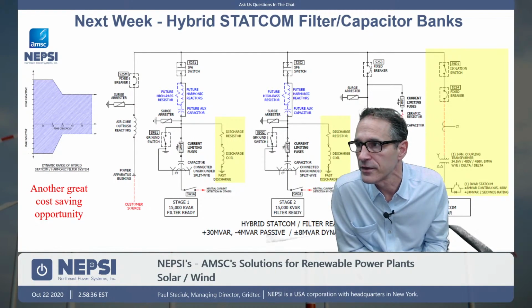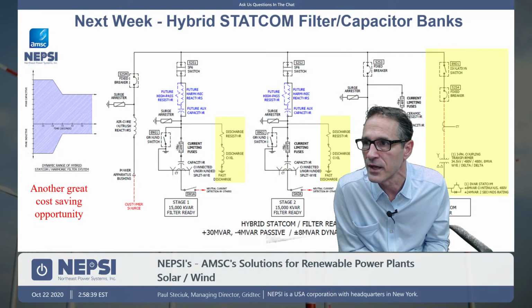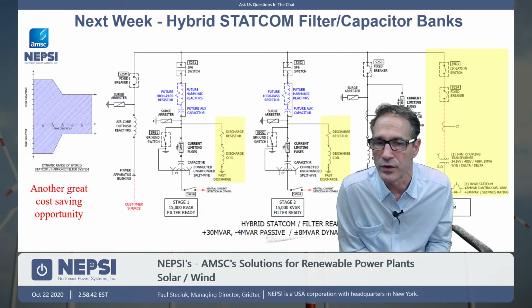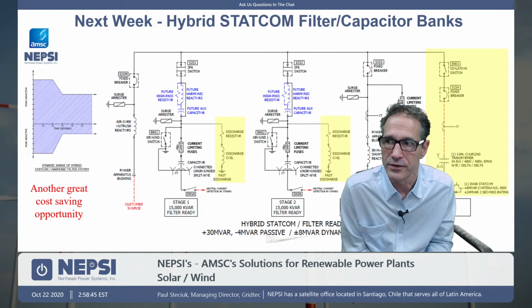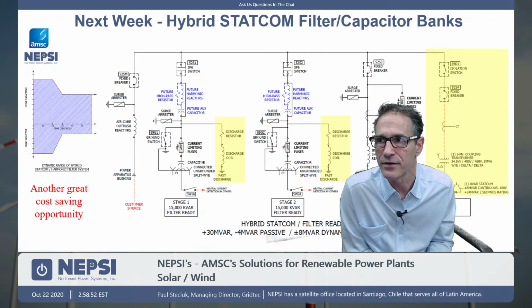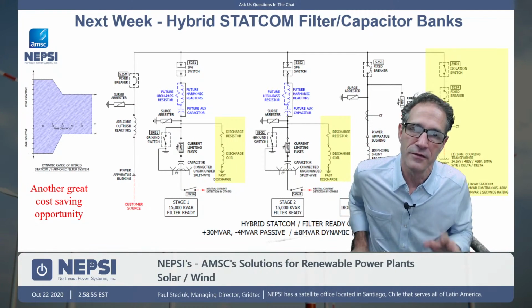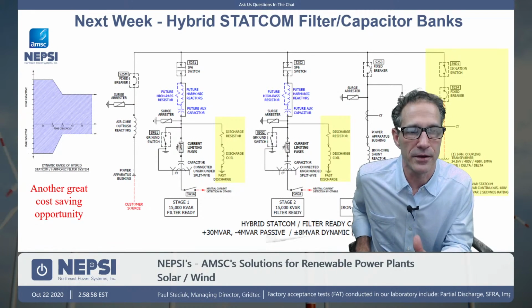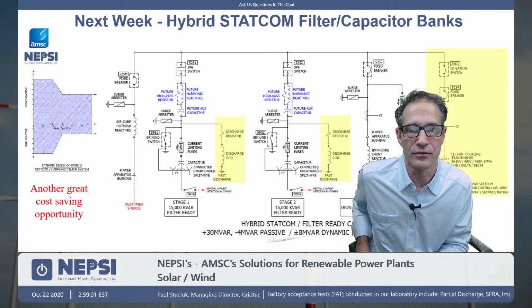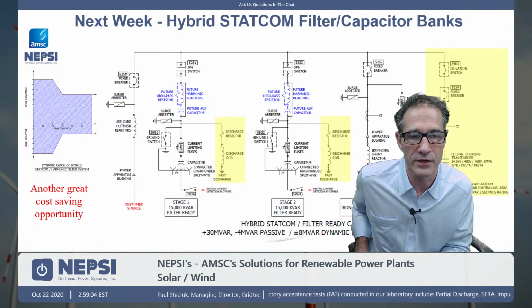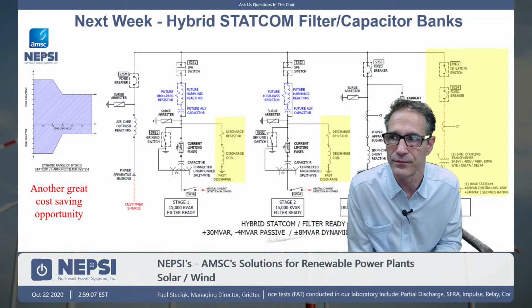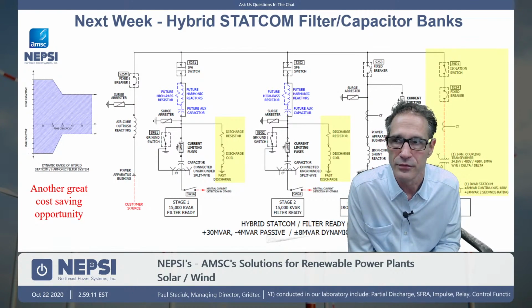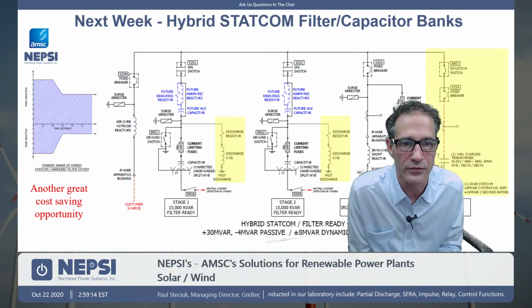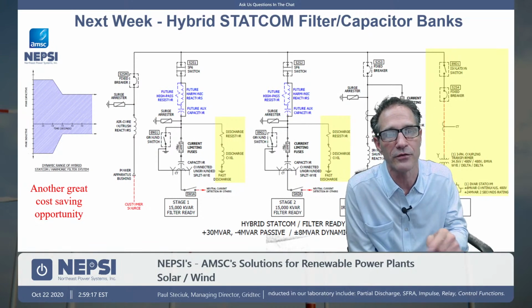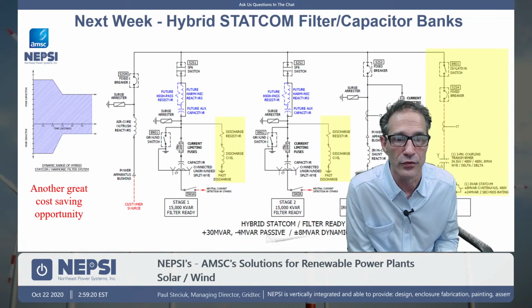Okay, so Talit asked, what is a good filter type to dampen natural harmonic resonance point at around the 40th harmonic? Here I would say that you would want to consider a C high pass filter. No, actually, I take that back. C high pass filters, 5th harmonic and down. Here would be a high pass filter. So standard high pass filter, tuned very high up. You would have to go with a pretty heavy damping factor up at that frequency to make a difference. So I would say you'd want to go with a relatively low damping factor. I want to make sure I get that right. Low damping factor to really flatten the curve and then tune around the 40th harmonic.